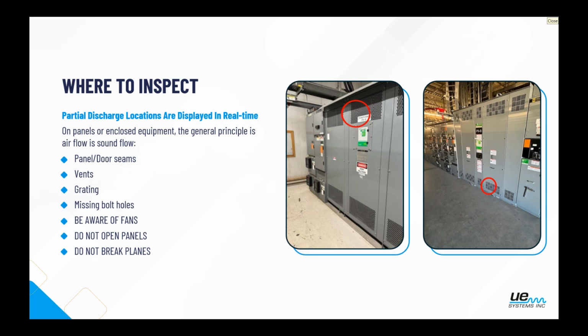If in this example we have grating on the top and the bottom, I would inspect on both. For the reason being, in these specific examples, we did an inspection. We heard a very strong partial discharge sound coming from the top on this left picture. But then when we inspected from the bottom, we heard the same event, but much more muffled. It could have honestly been missed if someone had not been taking their time. Because once again, sound is very directional, we heard a stronger signal from the top. So definitely an issue going on, but we also had a much better sound quality recording from the top than we would have from the bottom.